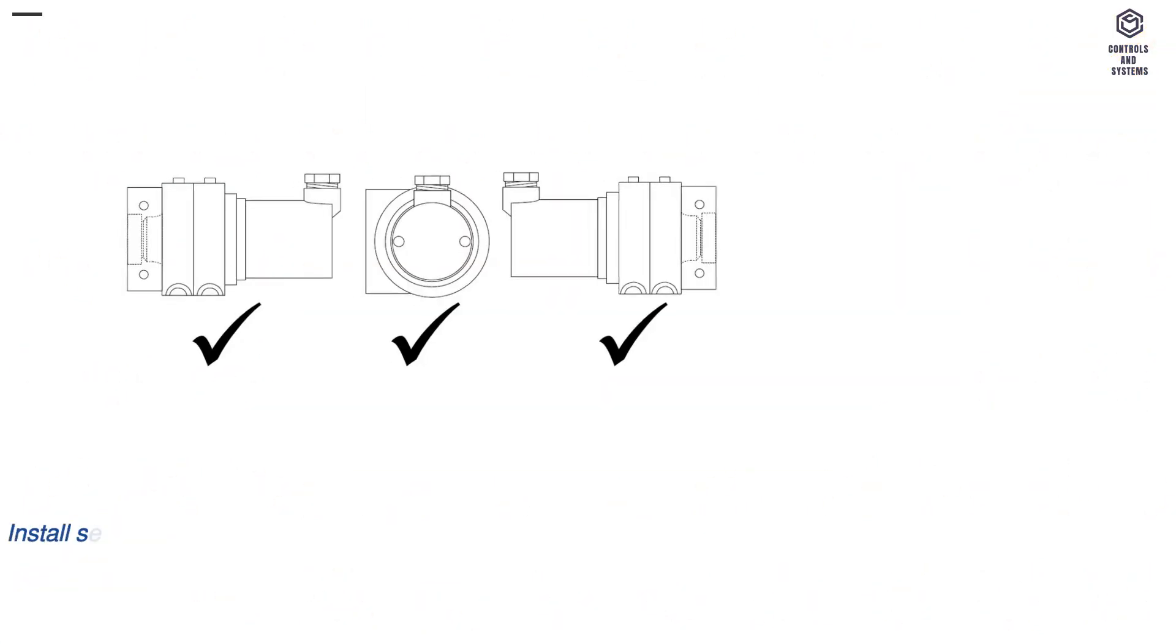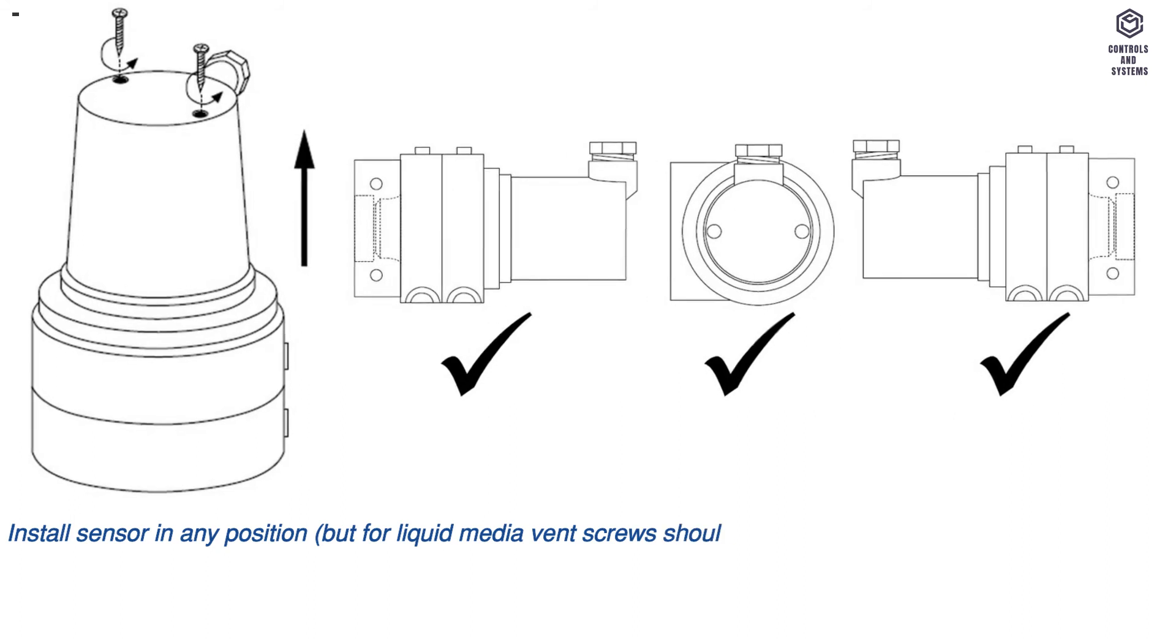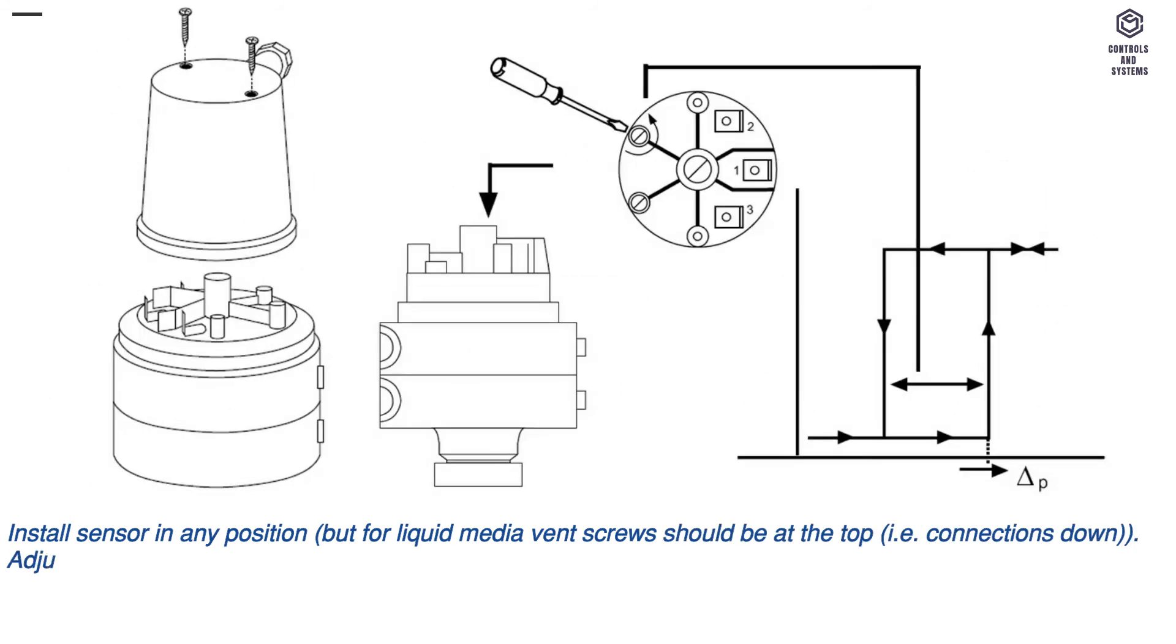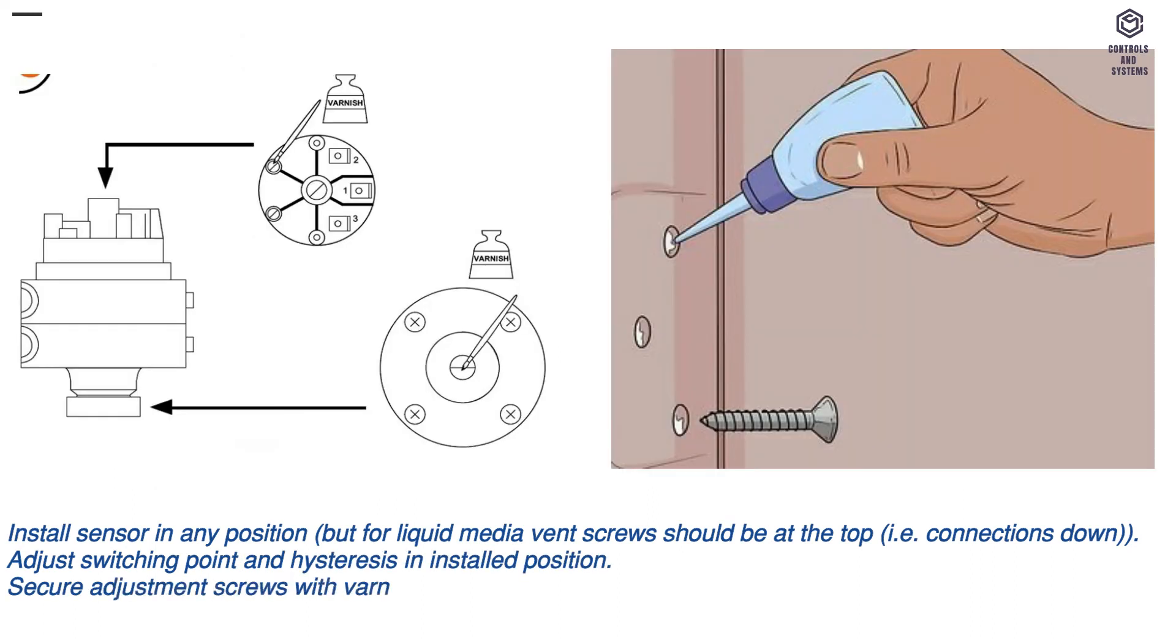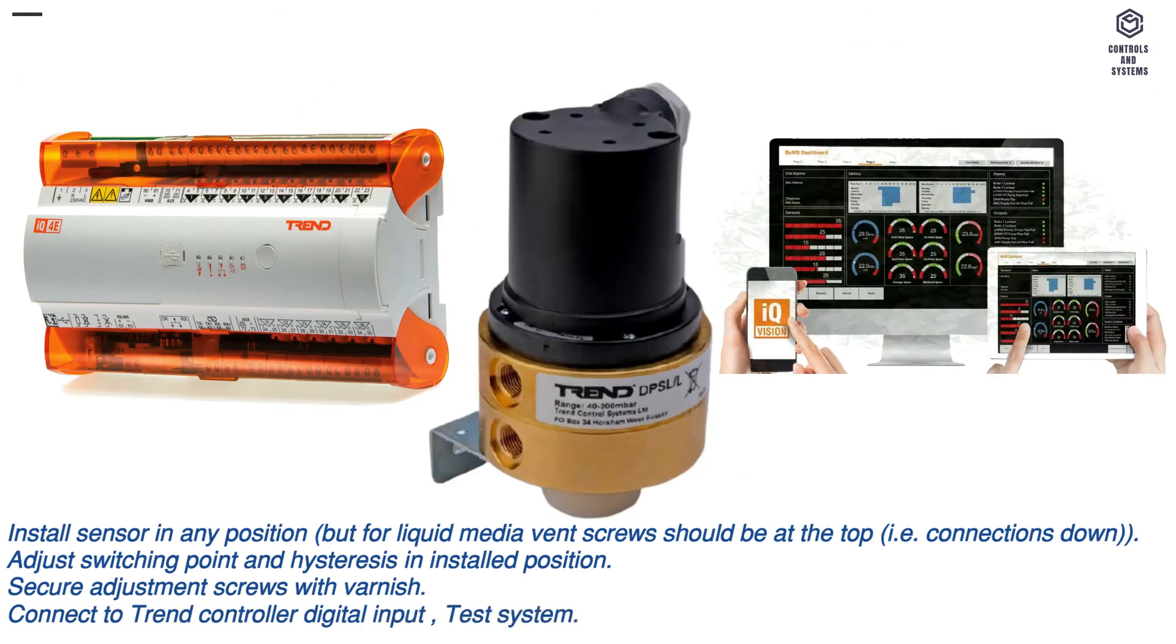Installation: install sensor in any position, but for liquid media vent screws should be at the top, that is connections down. Adjust switching point and hysteresis in installed position. Secure adjustment screws with varnish. Connect to Trend controller digital input. Test system.